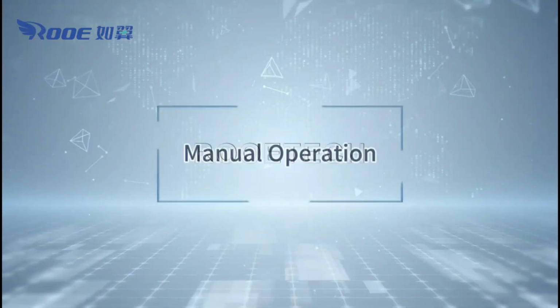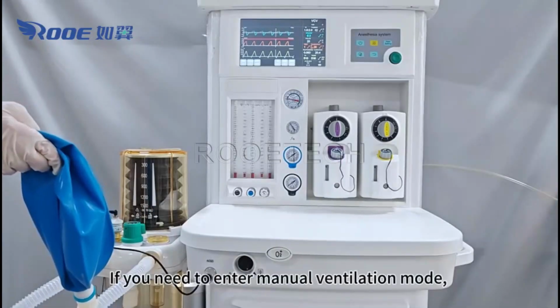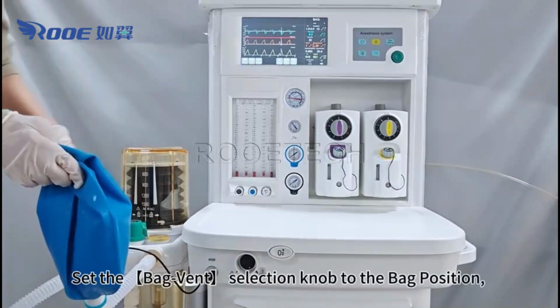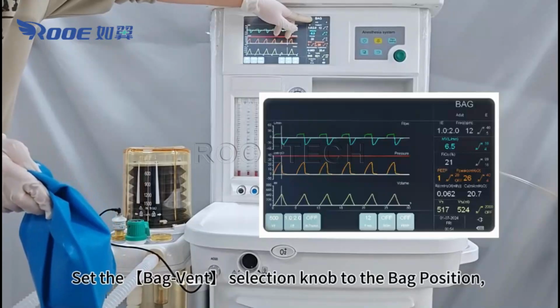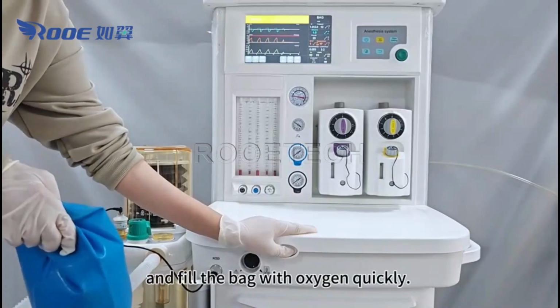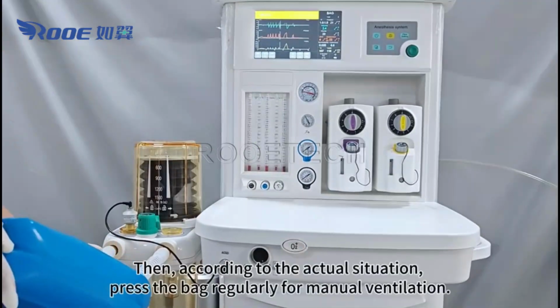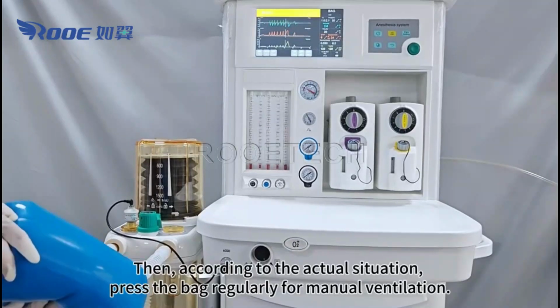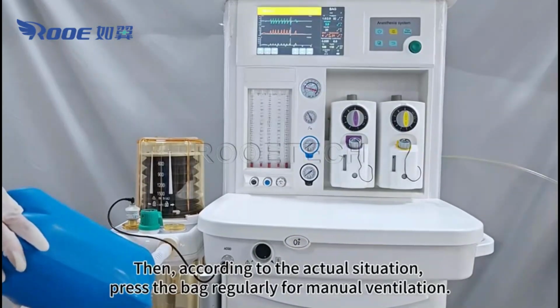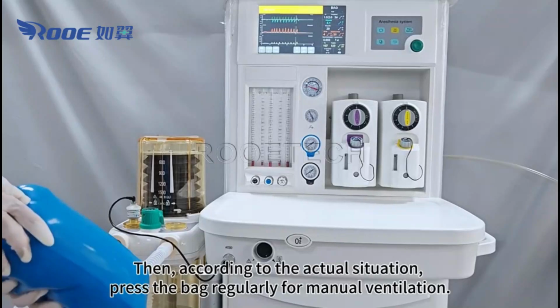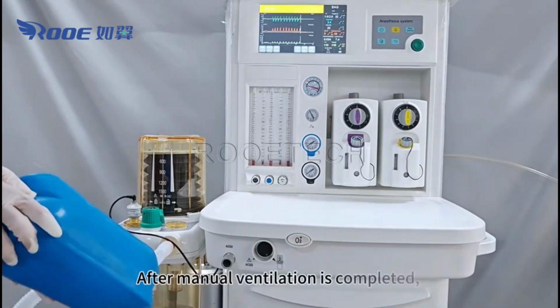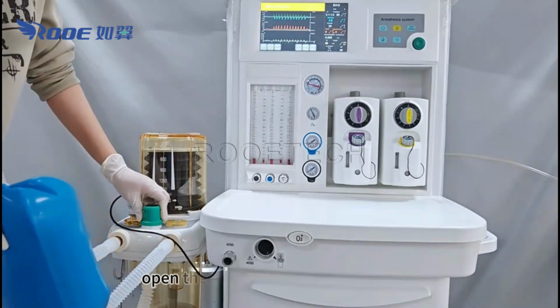Manual operation. If you need to enter manual ventilation mode, set the bag vent selection knob to the bag position and fill the bag with oxygen quickly. Then, according to the actual situation, press the bag regularly for manual ventilation. After manual ventilation is completed, open the APL valve to release the gas.